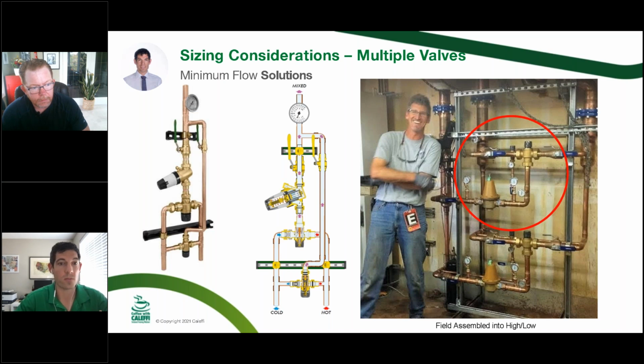But there are different ways to do that, and they can also be a little tricky to set. There's no specific number on that PRV that you're going to set that's going to work for all job sites. There is some commissioning involved with that to make sure that the bigger valve is coming on at the right time. Yeah, so it's a very viable solution, but the reality is that whether you're the engineer designing it or the contractor installing it, this wouldn't be my first choice today.